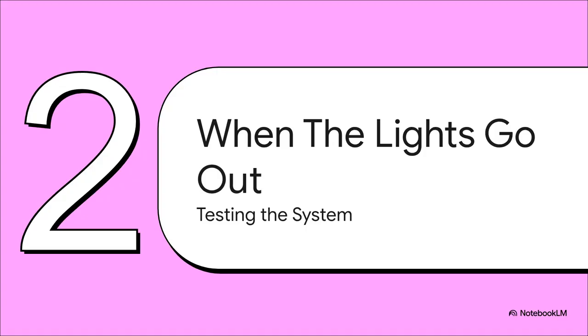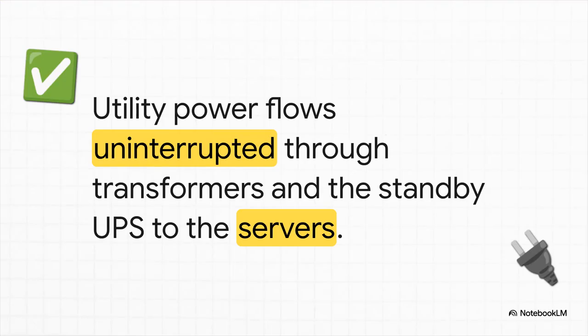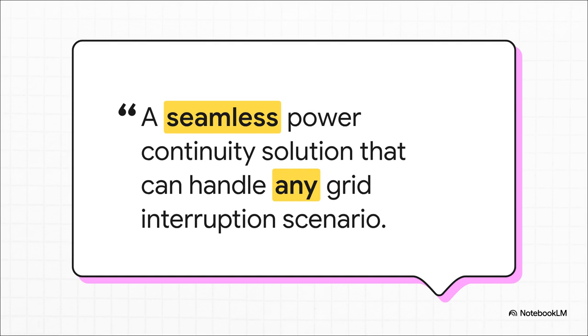All right, so we've designed our fortress, and we know who our key players are. But how does it actually hold up under attack? Let's go ahead and simulate a blackout and see what happens the second the main power from the grid gets cut. On any normal day, it's a pretty simple, calm flow. Power comes in from the utility, gets transformed, it passes through the UPS, which is just sitting there on standby, and it feeds the servers. Everything is stable, and all those backup systems are just waiting. And this, right here, is the core promise of the entire system. See, it's not just about having a backup plan, it's about creating a transition so seamless that the servers don't even have a clue that a failure has happened. So let's see how it delivers on that promise.